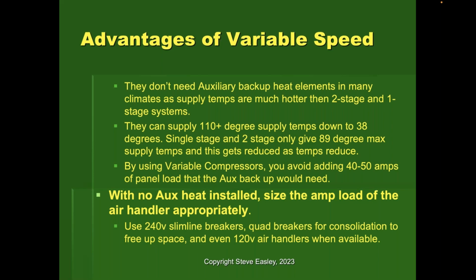By using variable speed inverter-driven compressors, you can avoid adding 40 to 50 amps of panel load in some cases. I think the system that I'm using, some of these things, their amp draw will be less than 10 amps at more traditional loads. So that's really important when it comes to this grid issue, and particularly if you have solar and you're doing battery backup. So, for example, in most parts of California, the electric utility rates are 50 cents a kilowatt hour between 3 and 8 o'clock at night.